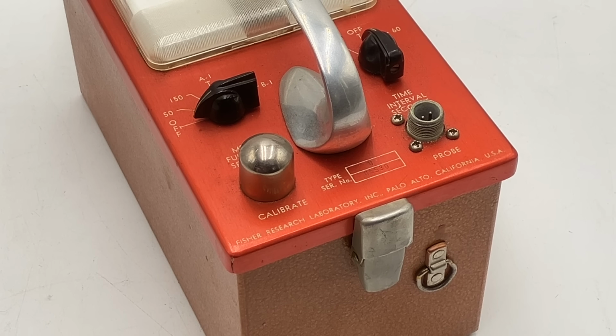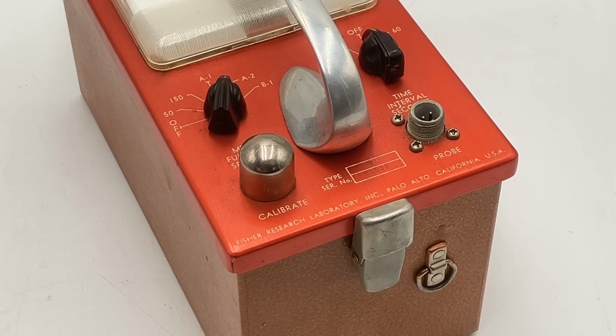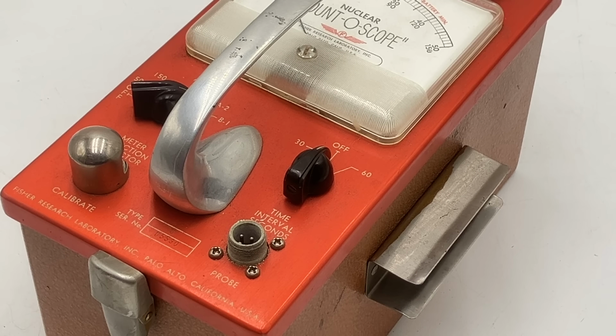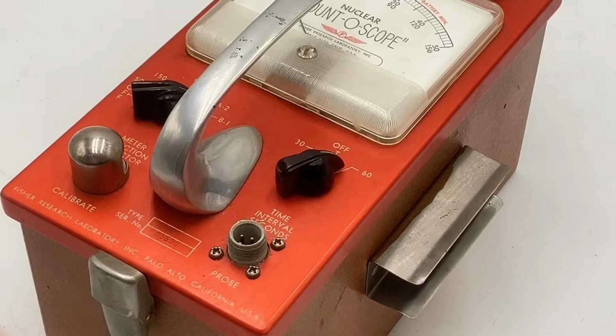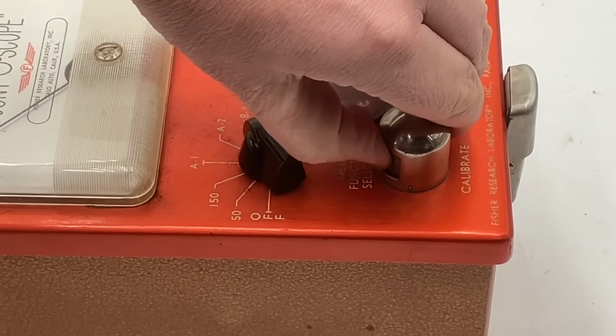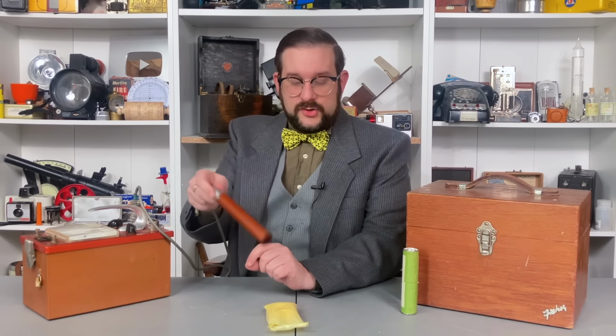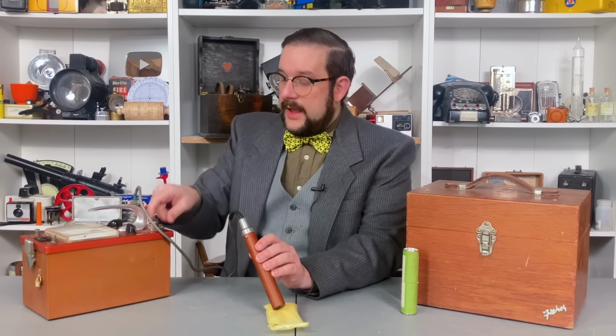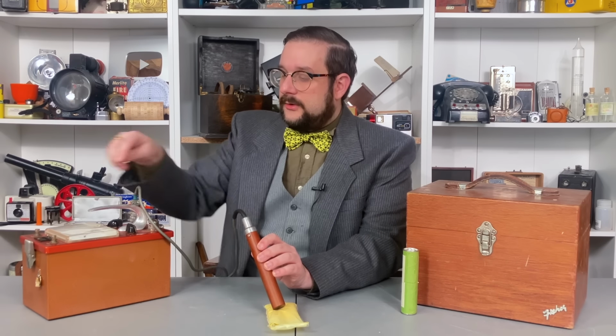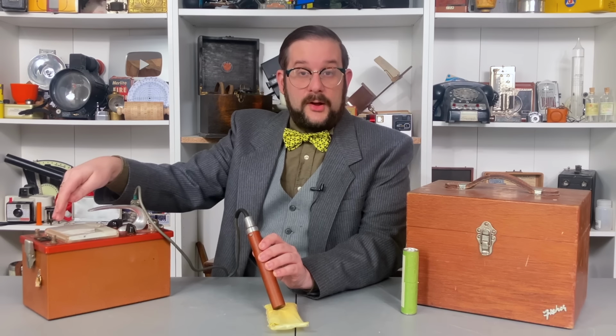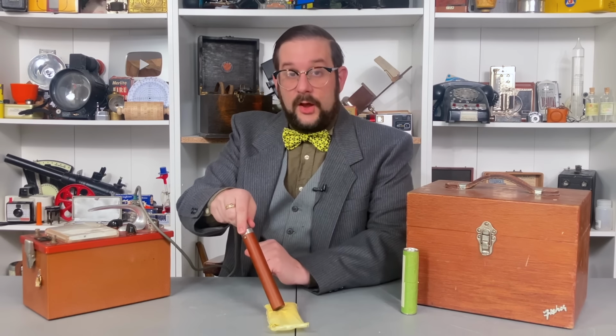The knob on the left has 6 positions: off, sensitivity range 0 to 50, sensitivity range 0 to 150, and 3 battery check settings for the A1, A2, and B1 batteries, which we'll have a look at in a moment. Meanwhile, the knob on the right has 3 positions: off, and the 30 and 60-second time intervals for the scaler. And finally, this is a calibration knob. To use this, you place the detection probe next to a check source, and then turn the knob until the readout on the dial corresponds to the standard activity of the source.